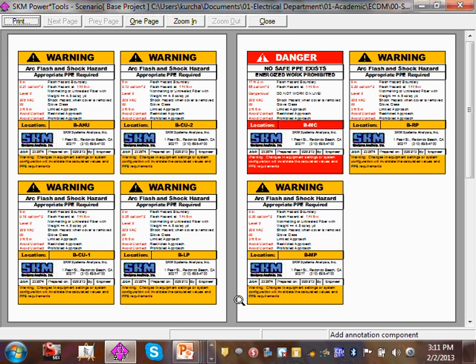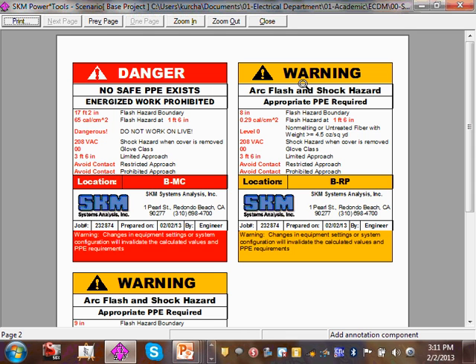From arc flash. What's the calories on that one? Let me zoom into it. Here you go. So the calories is 65, and category 4 can go up to 40. They make 100, I believe, but they're not recognized by 70E. We kind of say over 40, you can't work on it energized. That's exactly it, the blast will kill you. Yeah, because there are two things, right? There is the arc flash engulfed in the ball of fire, and then there's the pressure and the blast that's going to kill you. So that's 65.